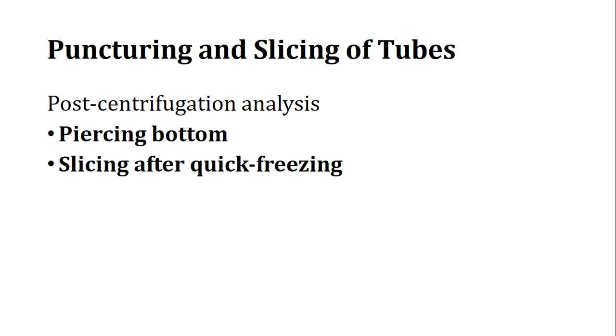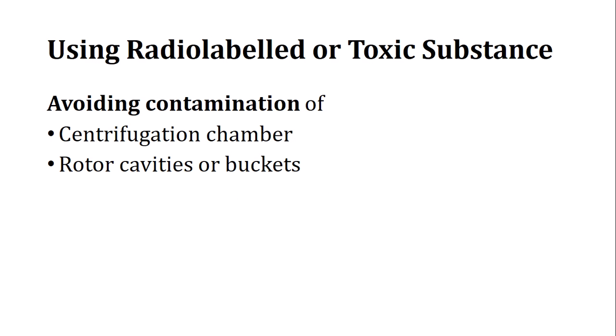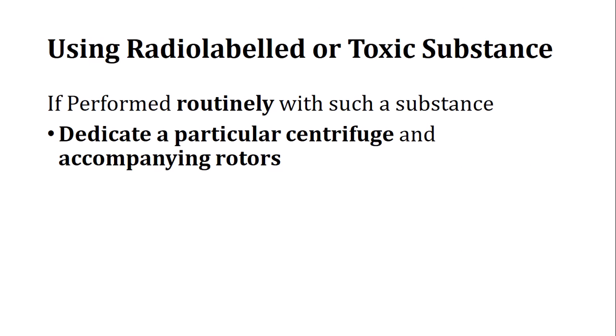For post-centrifugation analysis, two techniques can be used: piercing from the bottom or slicing after quick freezing. When using radiolabeled or toxic substances, contamination of the centrifuge chamber, rotor cavities, or buckets must be avoided. If routinely using toxic or radiolabeled substances, a particular centrifuge and its accompanying rotor should be dedicated for that purpose only.